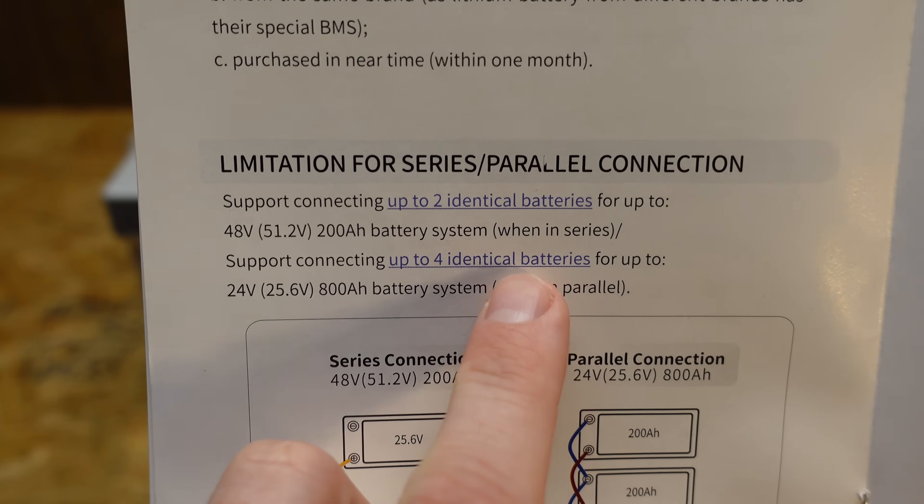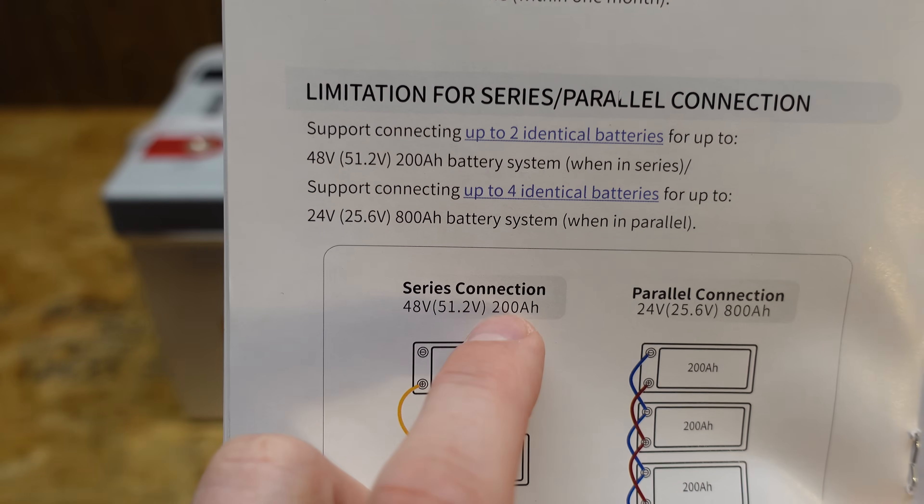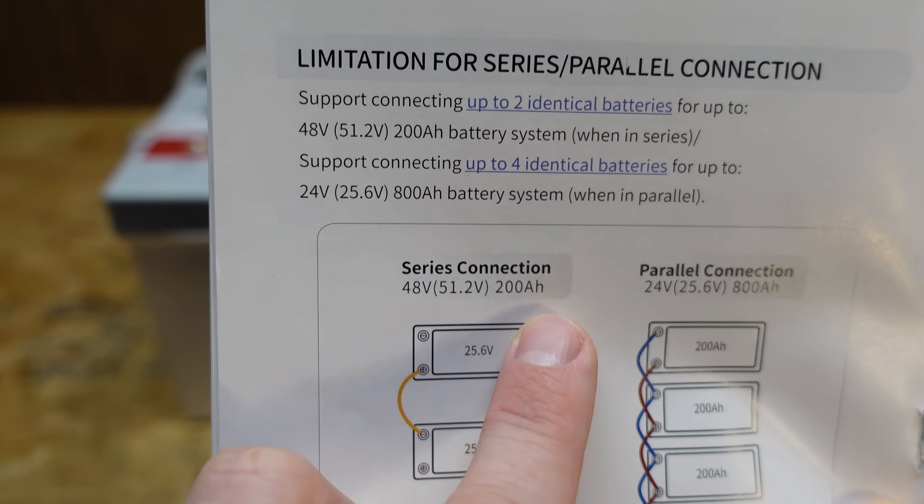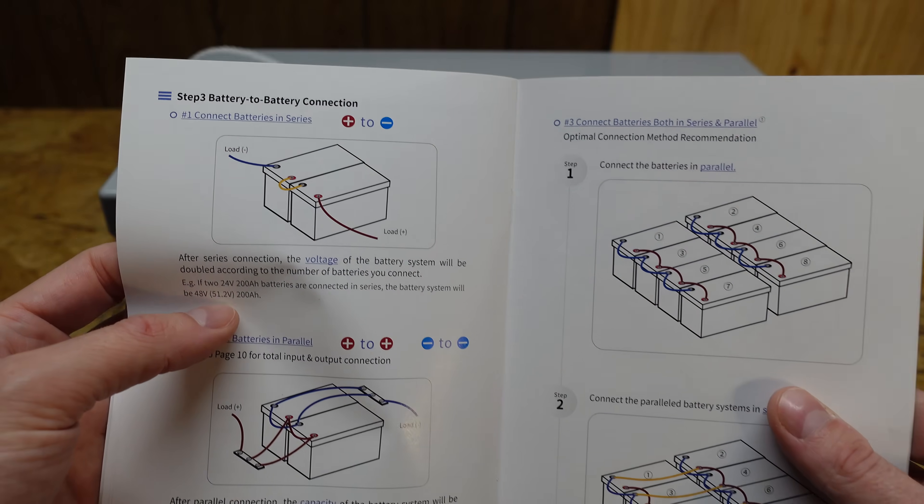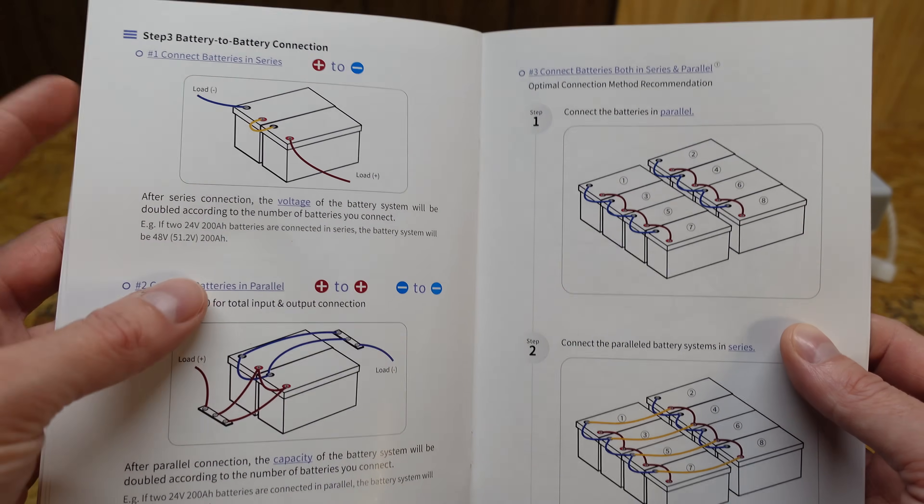So you can connect a max of two of these in series for a 48 volt battery, and you can connect up to four of them in parallel for an 800 amp hour battery. There's quite a few pages here explaining the series and paralleling steps.